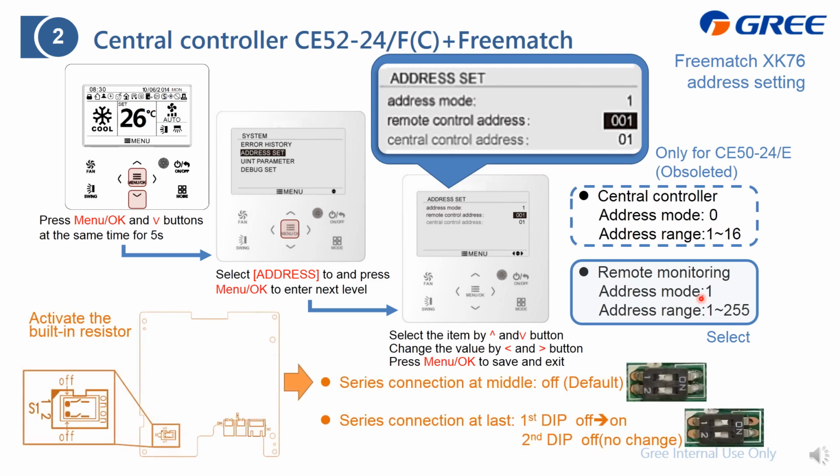The last thing is, don't forget to turn on the built-in resistor if this wire controller is located at the last, to ensure the communication. And also here is the dip switch, which is this one too. If it is located at the last, just change the first DIP from off side to on side, okay.